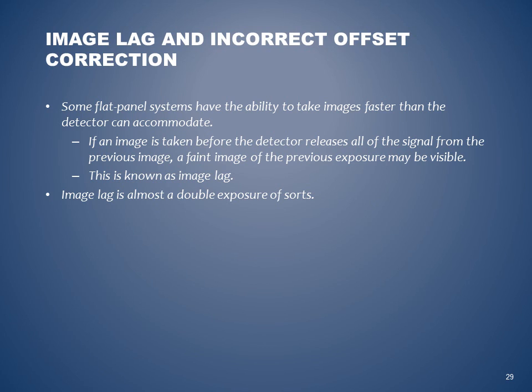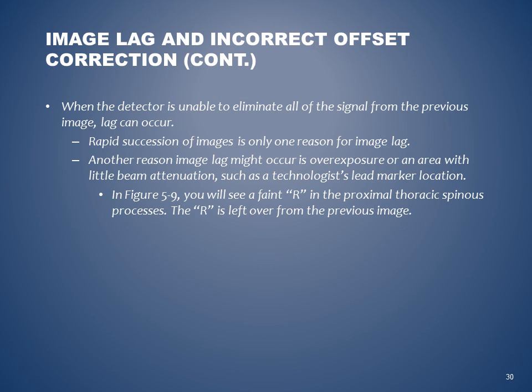Some flat panel systems have the ability to take images faster than a detector can accommodate. If an image is taken before the detector releases all of its signal from the previous image, a faint image of the previous exposure may be visible. This is known as image lag. Image lag is almost a double exposure of sorts. When the detector is unable to eliminate all of the signal from the previous image, lag can occur. Rapid succession of images is only one reason for image lag.